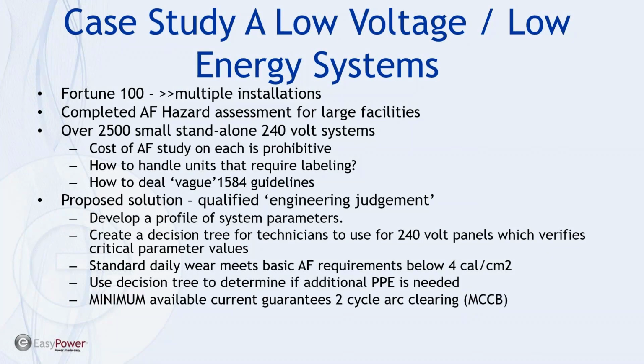All right. So moving on, let's talk about our first case study. The situation occurred with a very large U.S. company that has multiple plants and multiple installations. They'd completed the arc flash hazard assessment for their large facilities, but they understood that they have over 2,500 small standalone 240 volt systems, and the cost of doing studies on each of these standalone installations is prohibitive. So the request was, how do we handle the labeling requirements?